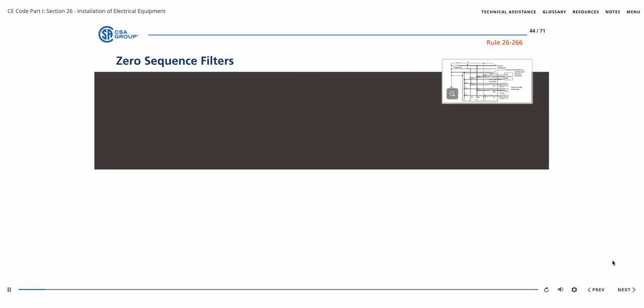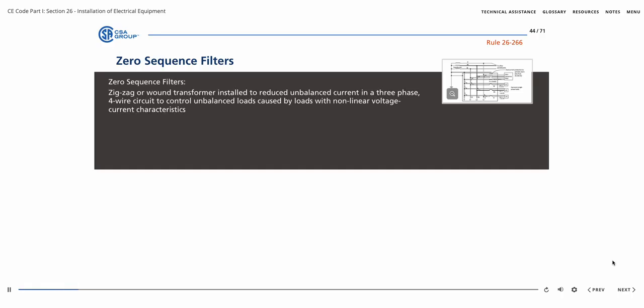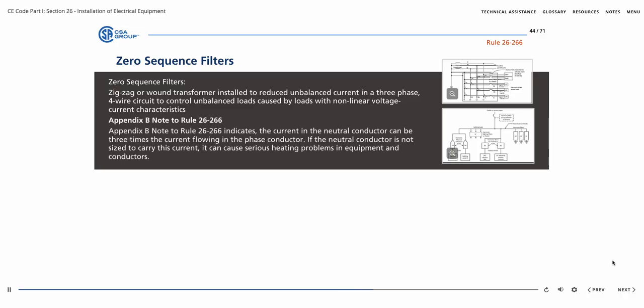Another type of transformer is the zigzag transformer. Zero-sequence filters are zigzag or otherwise wound transformers used in a three-phase, four-wire system to control unbalanced loads that are caused by loads having non-linear voltage current characteristics, harmonics. In these installations, the neutral conductor can carry more current than the unbalanced current from other ungrounded conductors of normally balanced circuits of single-phase, three-wire, and three-phase, four-wire systems. Note the location of harmonic filters in the diagram. Appendix B, note to Rule 26-266 indicates the current in the neutral conductor can be 3 times the current flowing in the phase conductor. If the neutral conductor is not sized to carry this current, it can cause serious heating problems in equipment and conductors.